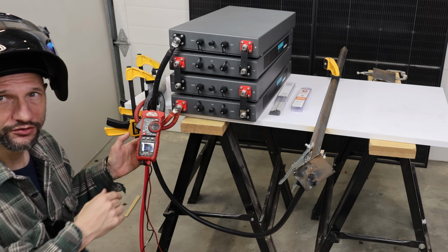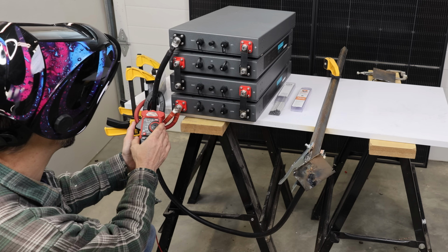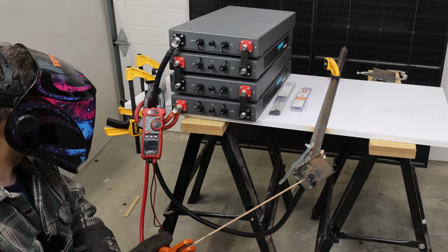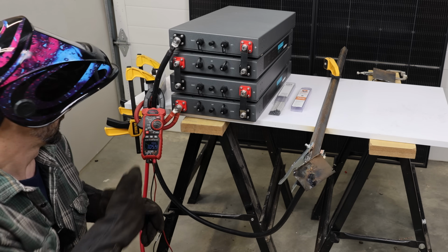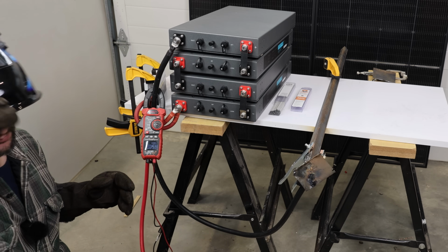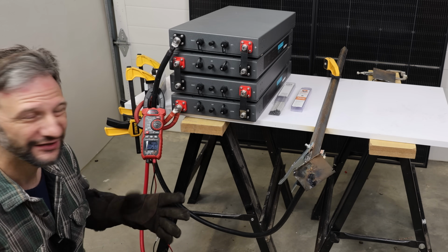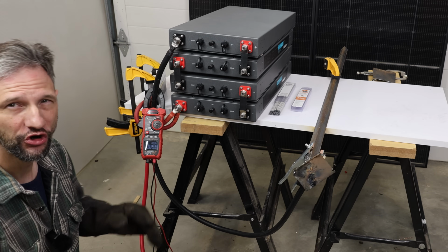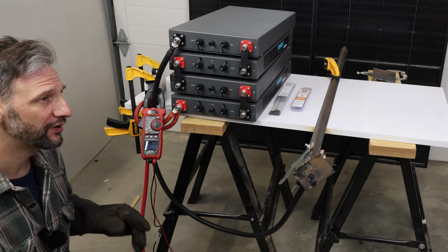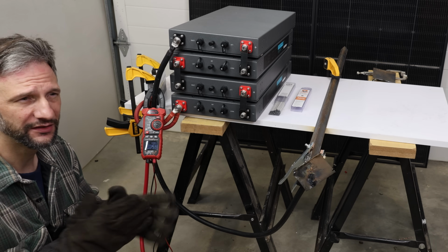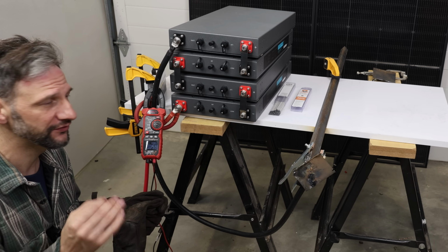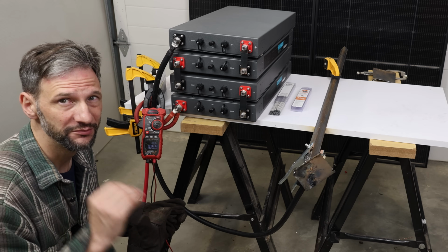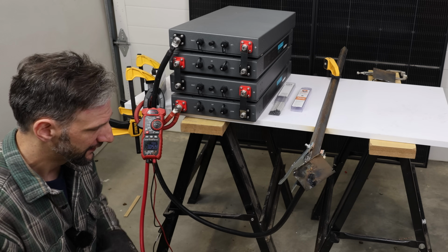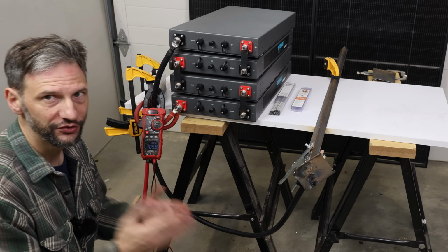I could put this on inrush and see how much it's actually registering. It's only showing 105 amps, but it's probably a little sharper than that, a very sharp ramp up, and the BMS is designed to pick up those very sharp spikes as a short circuit. That's what it should do. You want it to immediately shut down if there's a short circuit. It's just not really configured to be a welder.